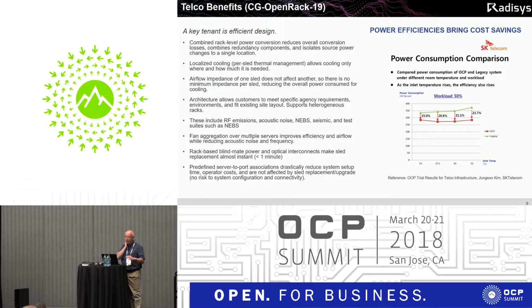But some of these that I'll mention, of course, by having cooling in each of the installed sleds, the cooling is controlled on a sled-by-sled basis. It allows you to have a heterogeneous configuration. So instead of, for example, having a rack that maybe Facebook would have where everything in the rack is identical, we're now talking about a smaller configuration where the racks or the sleds could be quite different. And you could upgrade as you go. So you move from, for example, a low power sled to a high power sled. There's no other change to the rack. Each sled is independent in that case.